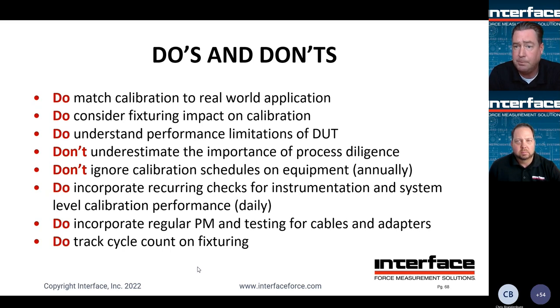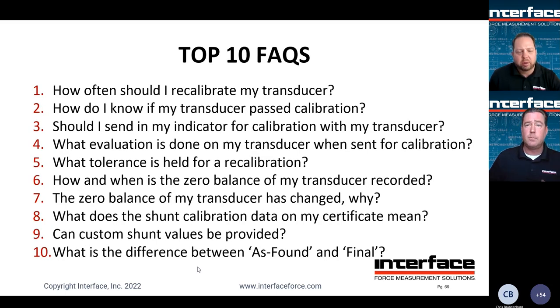Brian, anything else to add there? No, I think that's pretty good. The recurring checks are important. Interface employs various daily and weekly checks on all of our cal frames to ensure that we're maintaining consistent performance and, of course, recognizing if there's an issue. But the daily checks, coming up with a process there, is a very, very good recommendation for busy cal labs.